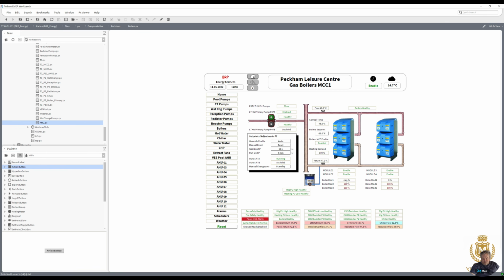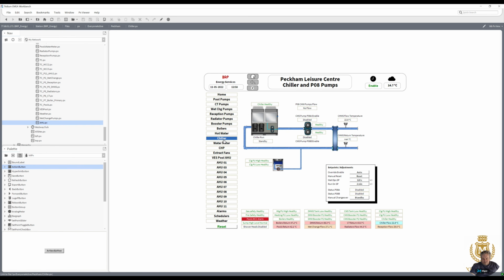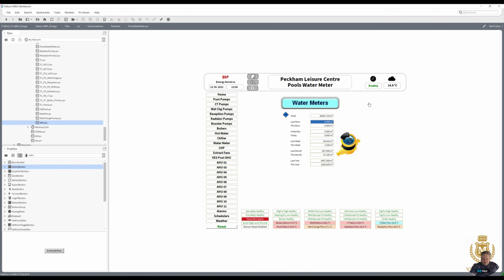That hasn't got a value, none. That sensor's gone faulty there as well, but I know that's gone faulty because I remember last time I went onto site I reported that sensor wasn't working and it wanted replacing, and this chiller's not working at all really. Yeah, it's disabled. But then again it's a bit cold. Well, at 14 degrees, no, it's not that cold outside.